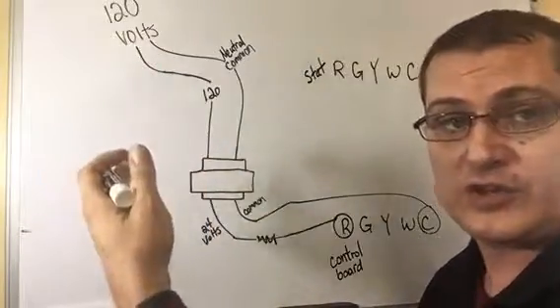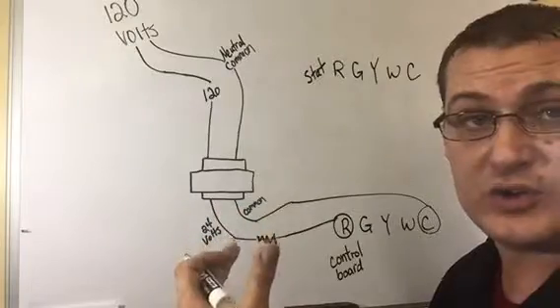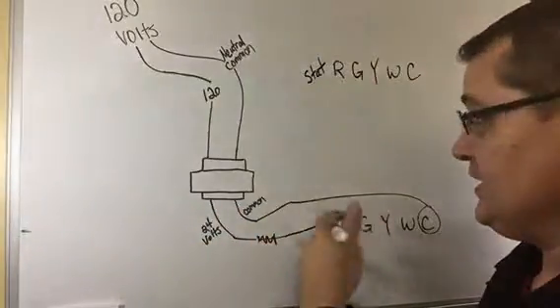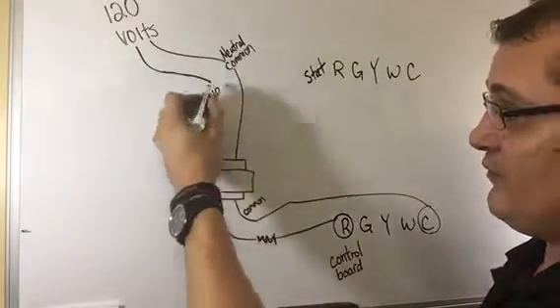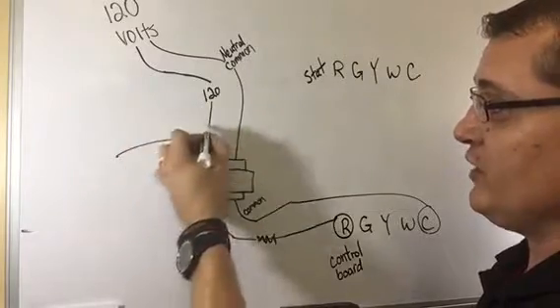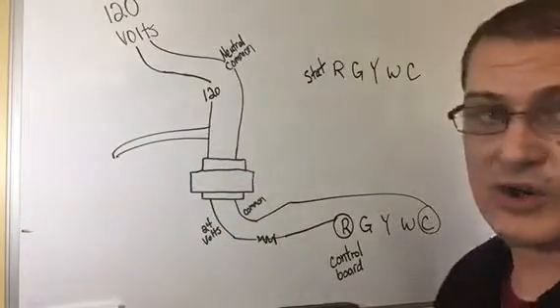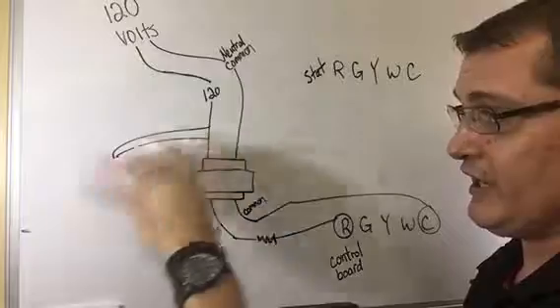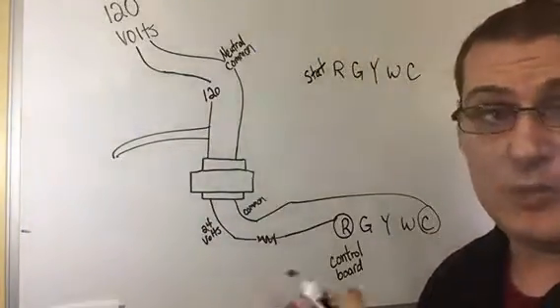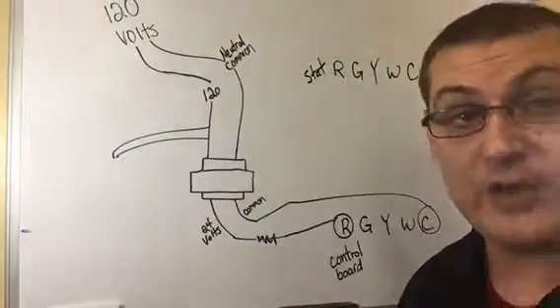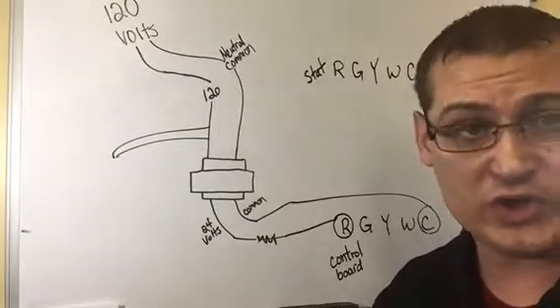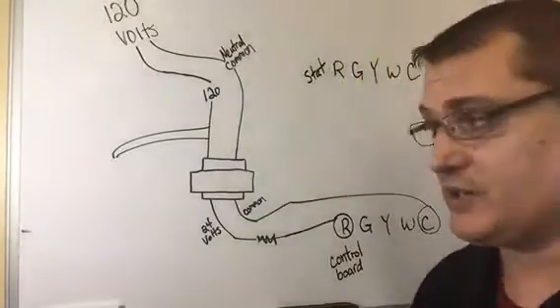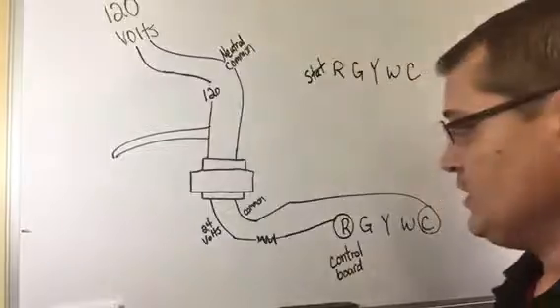This is basically what's happening in a furnace. You apply 120 volts, it's going to hit the transformer for your low voltage controls. This 120 volts will also split off and go to power, normally it goes to the board. And from the board, it's going to power the transformer. That way, the board has the 120 volts to control the motors and the ignition sequence or the igniter.